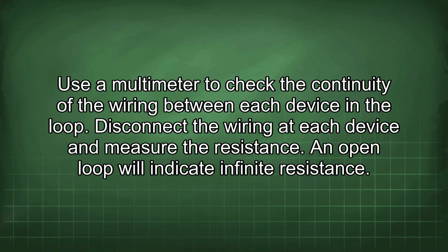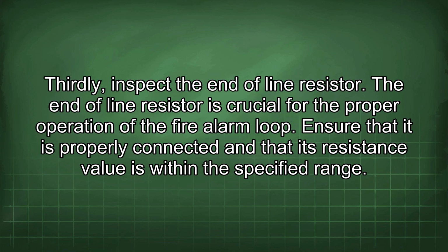An open loop will indicate infinite resistance. Thirdly, inspect the end-of-line resistor. The end-of-line resistor is crucial for the proper operation of the fire alarm loop. Ensure that it is properly connected and that its resistance value is within the specified range.